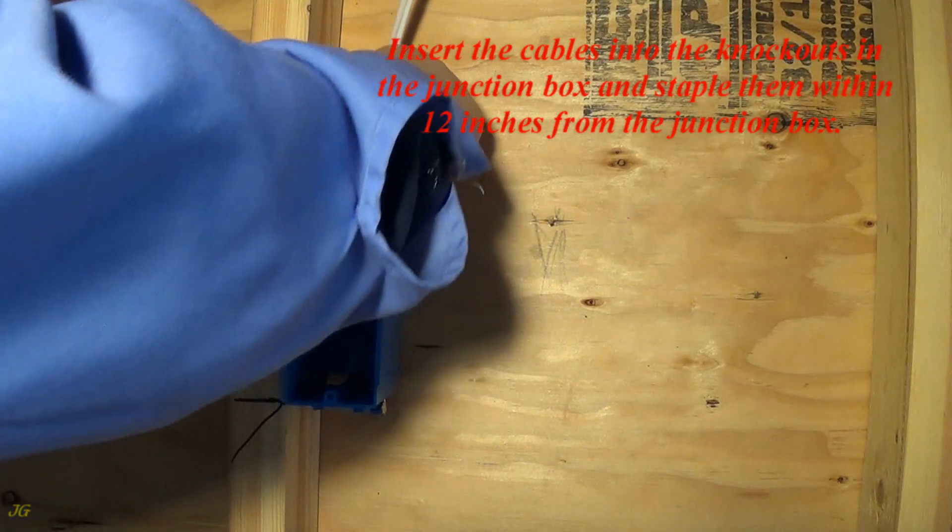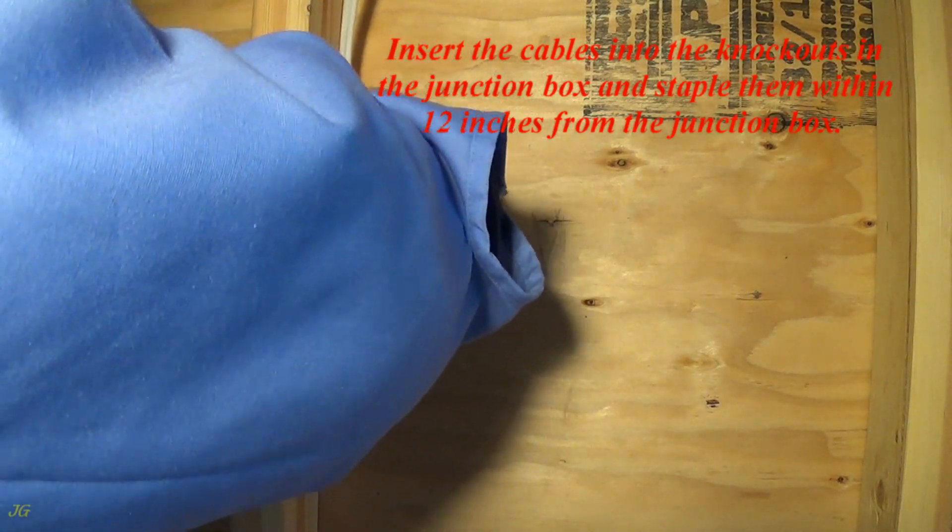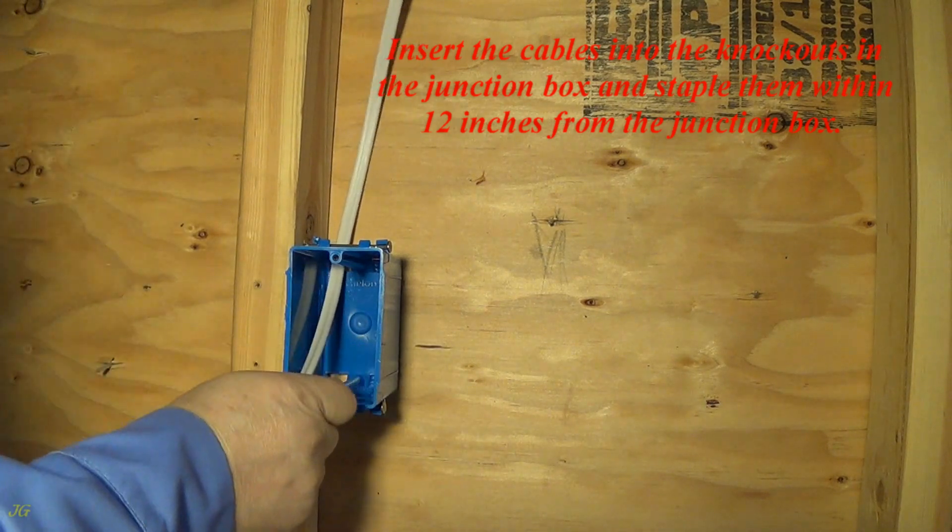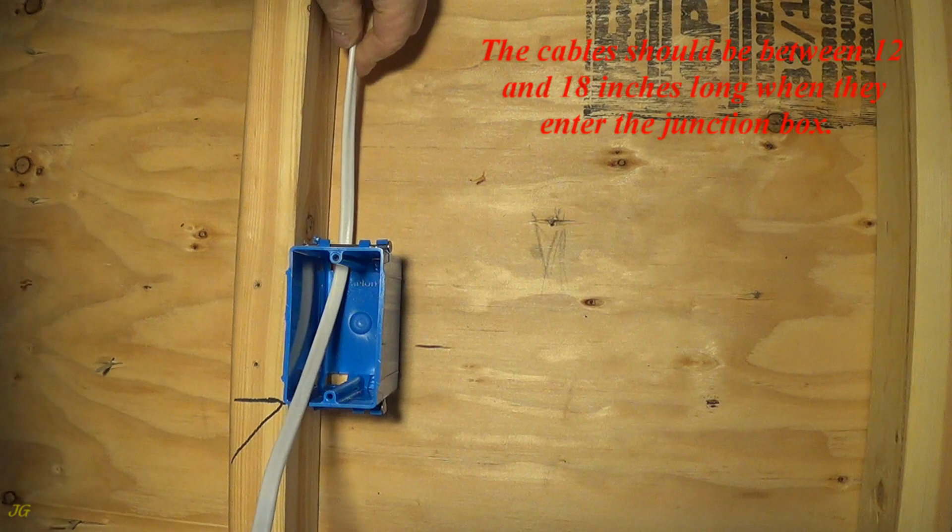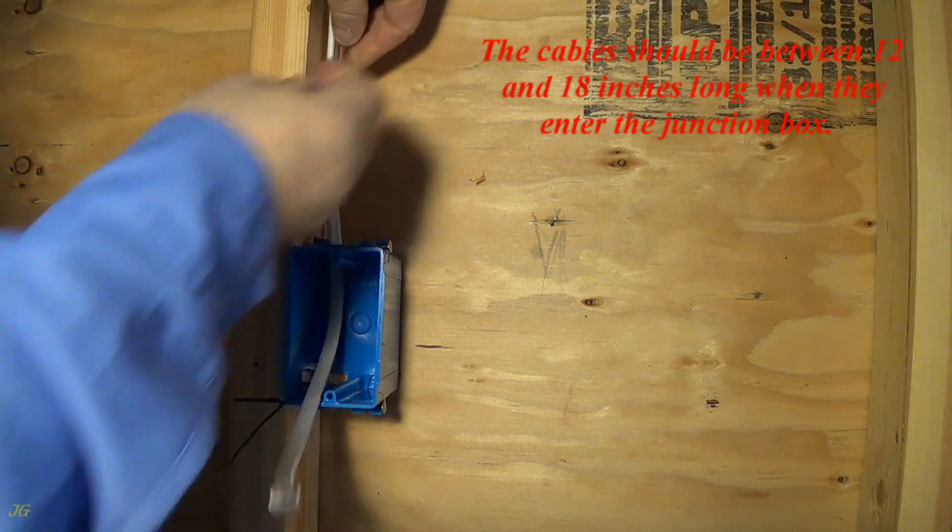Insert the cables into the knockouts in the junction box and staple them within 12 inches from the junction box. The cables should be between 12 and 18 inches long when they enter the junction box.